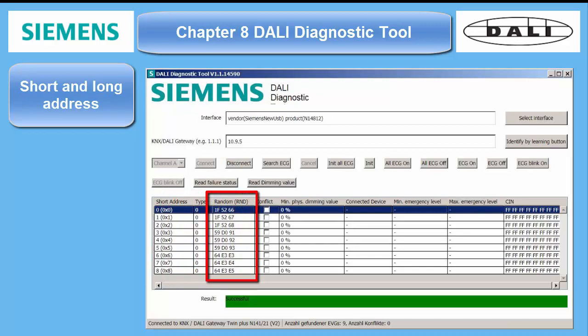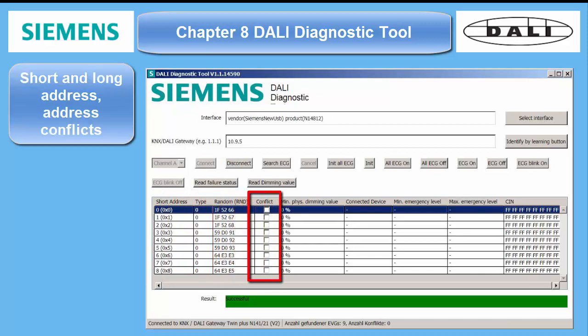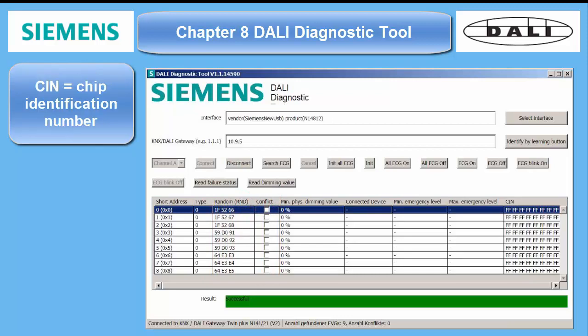The list contains info about short and long address, the random address, if there is an address conflict, and four more properties of the ballast if available. The last column shows the CIN — chip identification number — which is presently used only by OSRAM.